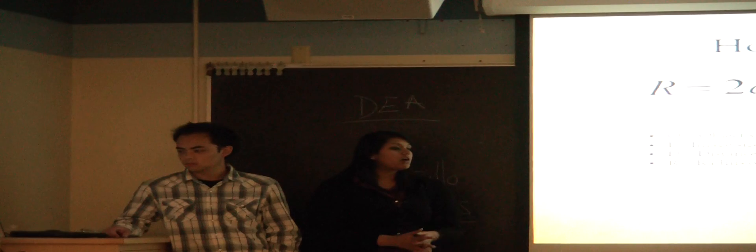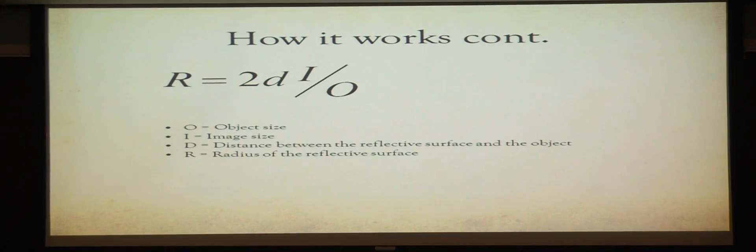The equation that the keratometer uses is this equation right here. There's a relationship between the radius of the reflective surface and the distance between the reflective surface and the object, image size and object size. So to determine three of these four variables, you can actually use one of the two principles, Javal-Schiotz or Bausch and Lomb.